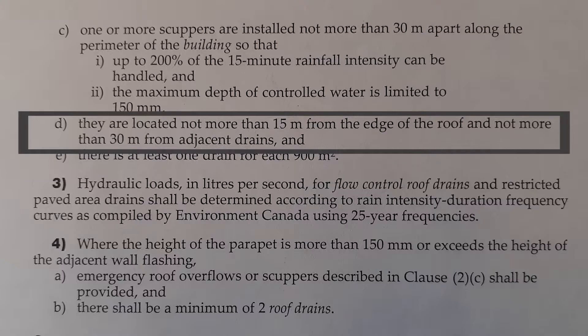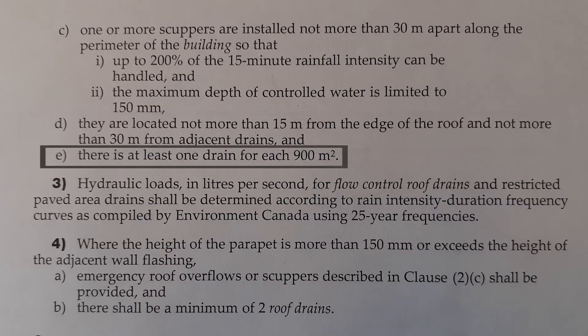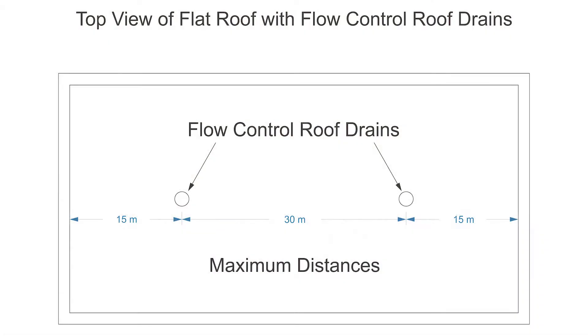Drains are not located more than 15 meters from the edge of the roof and not more than 30 meters from adjacent drains. And part E states there is at least one drain for each 900 square meters. This is to do with the location of the roof drains on the flat roof.